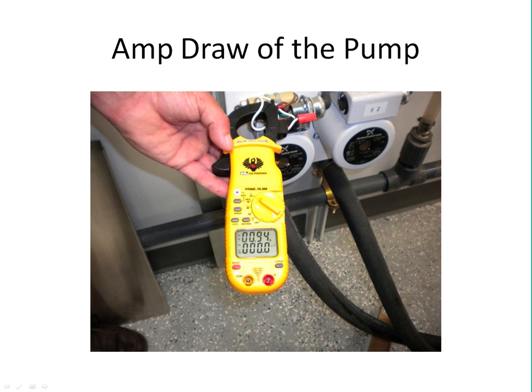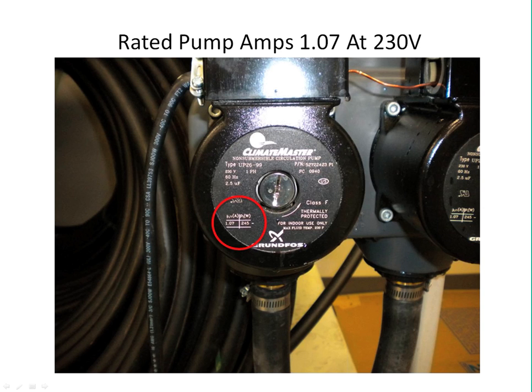I mentioned earlier, if you wanted to determine if the ground loop pump was appropriately drawing enough amps, here's an example that we took. This pump is operating and it's drawing about 0.94 amps. Well, here's the electrical rating of the typical Grundfos 26-99 pumps. Its specification shows about 1.07 amps, so the 0.94 is awfully close, and that shows that that pump is actually under load. Again, that's a good appropriate test when you want to test a pump to determine, is it operating, is it delivering the goods? Because you can't see what's going on inside. This is a good test.